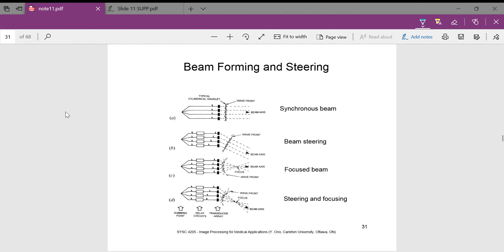Beam forming and steering: we are still talking about a linear array of transducer elements. Based on the timing of each electronic pulse at each element, different beam effects can be achieved. You can fire them all at the same time to get a synchronous beam; fire them with a linear time delay to get beam steering in a specific direction; fire them in a way that produces a focused beam — relating to our resolution and focal region — or do both, steering and focusing simultaneously. All of this is done simply by controlling the time at which each transducer fires.